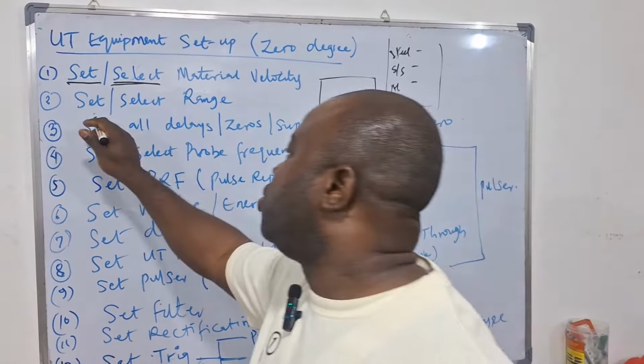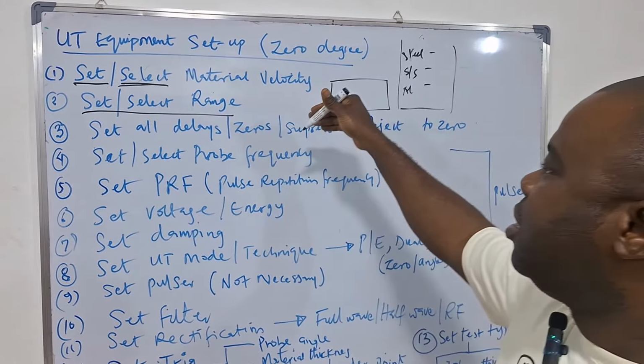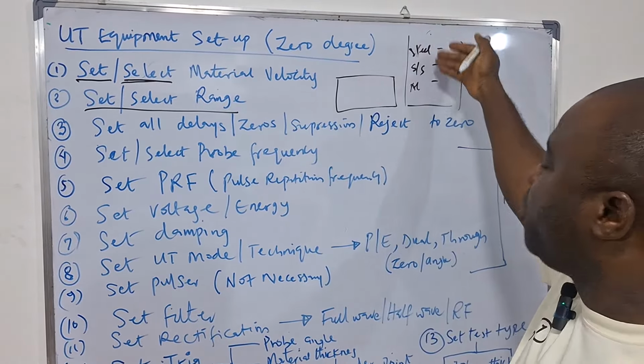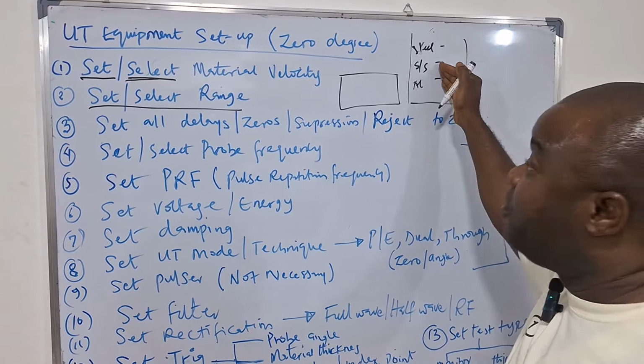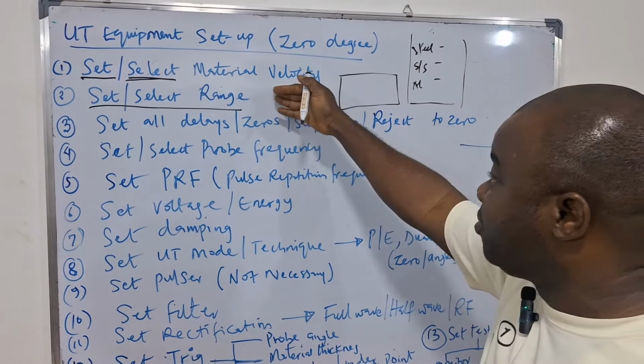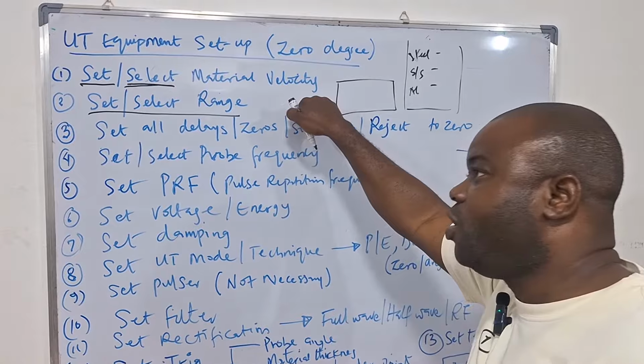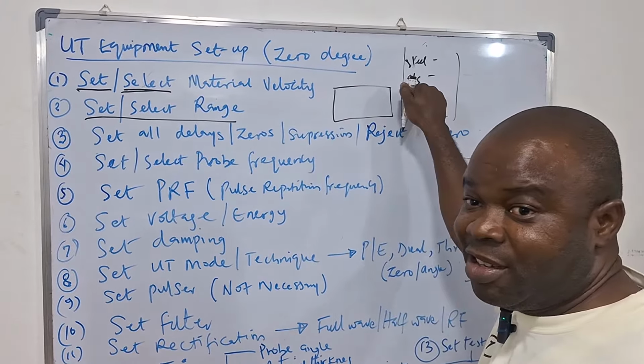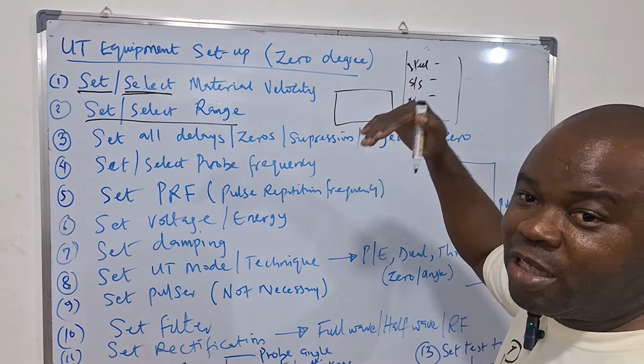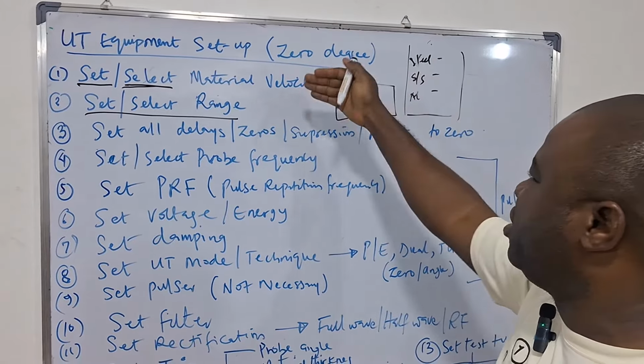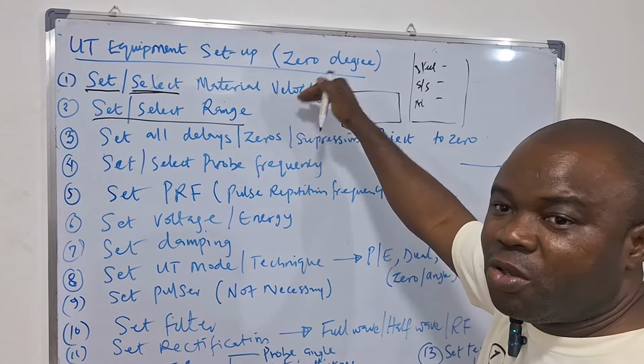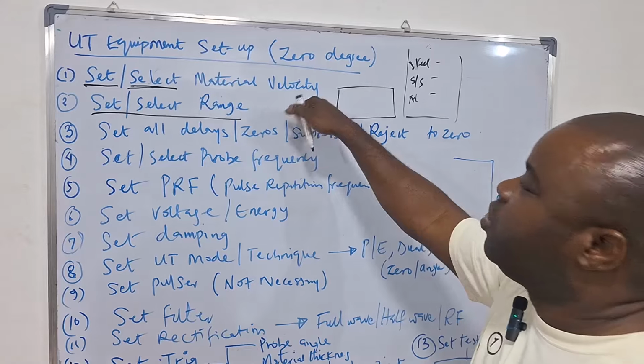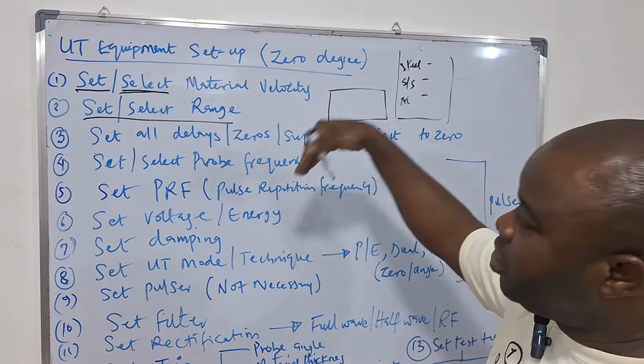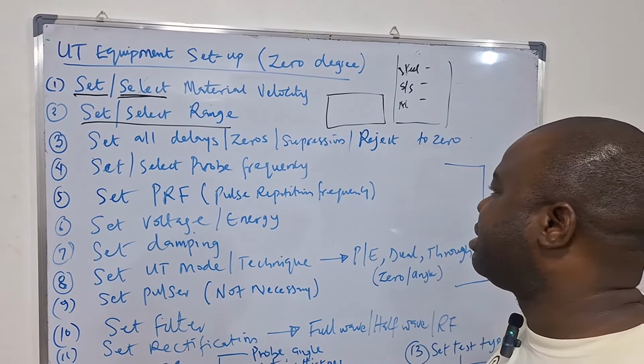The same applies to range. In some units, it gives you a drop-down with the possible ranges. A very popular machine for this with range is the Sonatest D50 -- you are forced to select. Even earlier versions of the D series give you options of the range you can take, so you just select. In other units, you are supposed to set it manually.